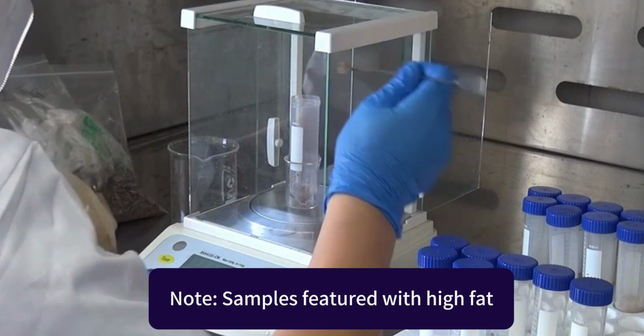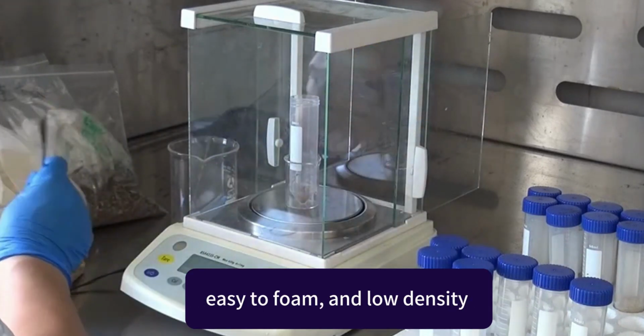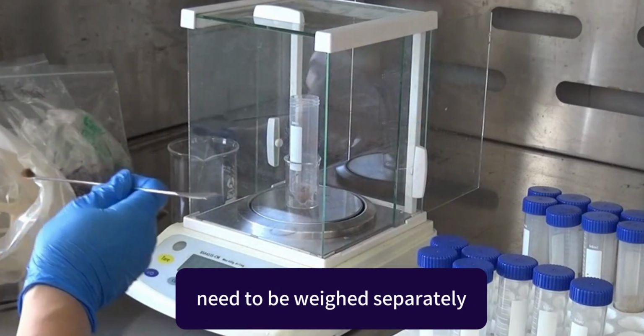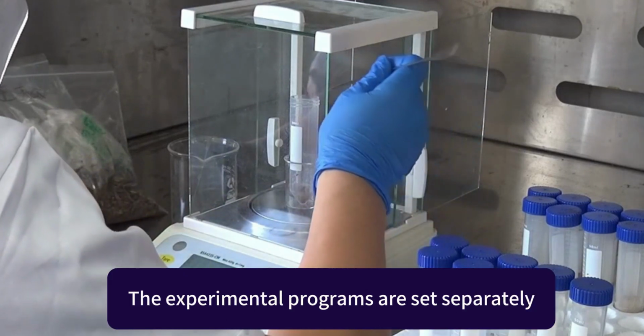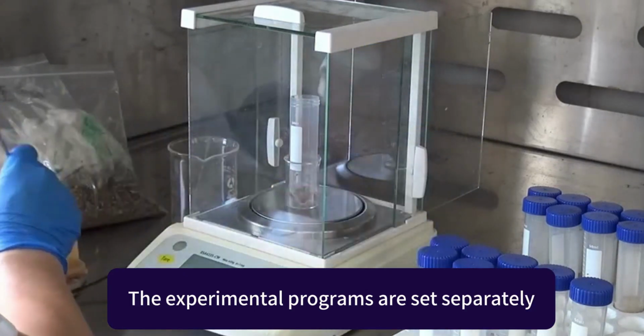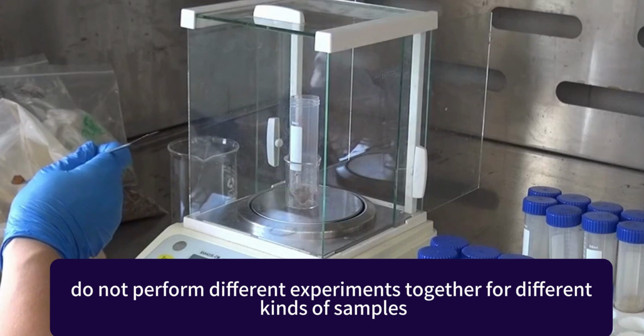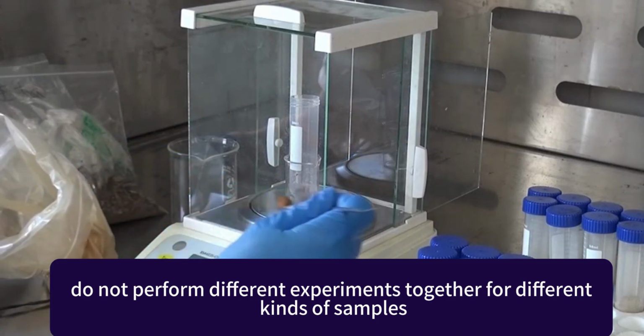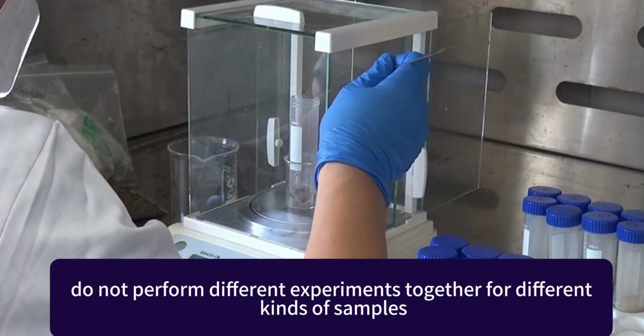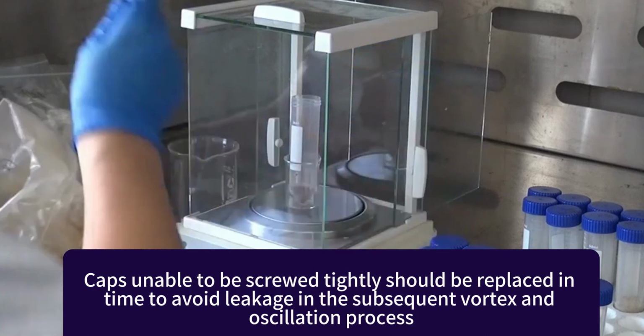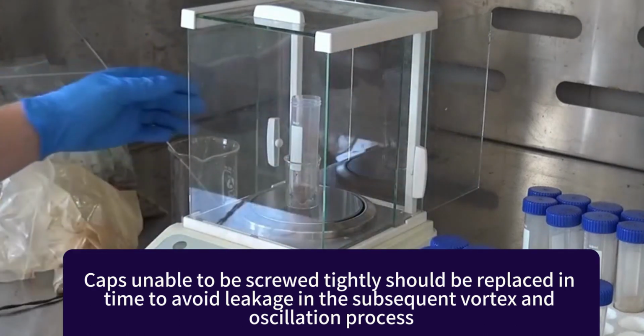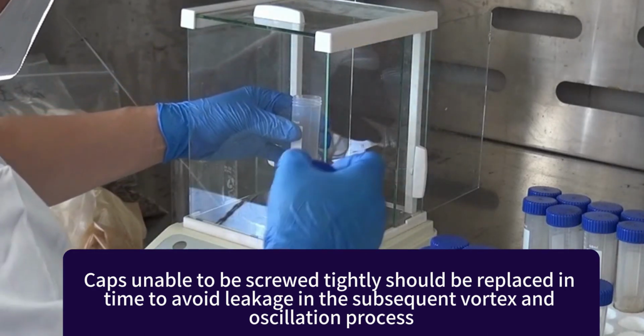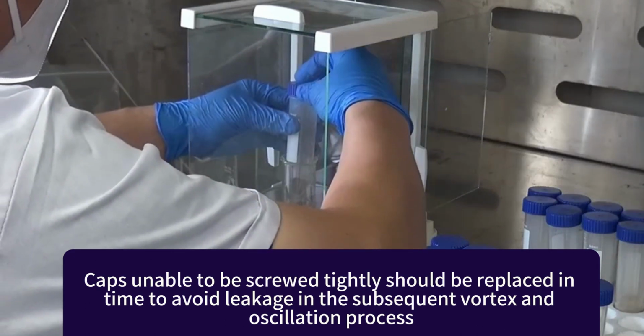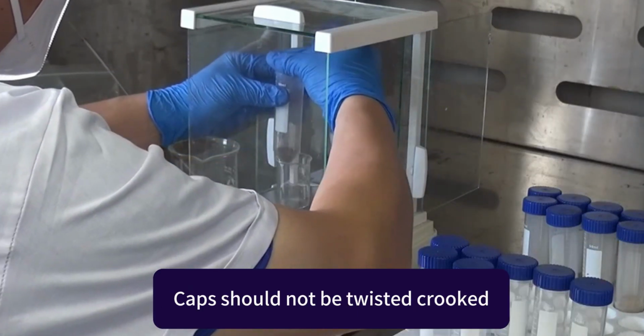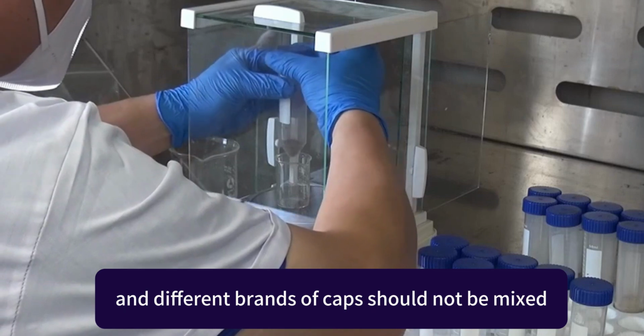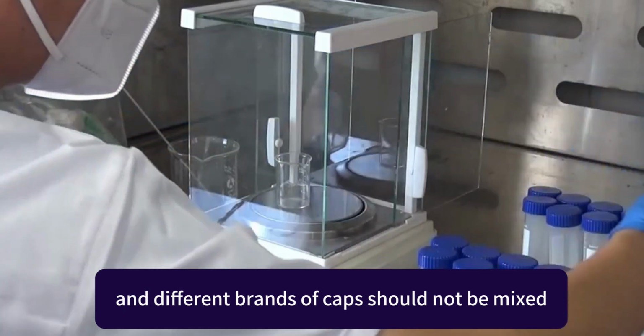Note: samples featured with high fat, easy to foam, and low density need to be weighed separately. The experimental programs are set separately. Do not perform different experiments together for different kinds of samples. Caps unable to be screwed tightly should be replaced in time to avoid leakage in the subsequent vortex and oscillation process. Caps should not be twisted crooked, and different brands of caps should not be mixed.